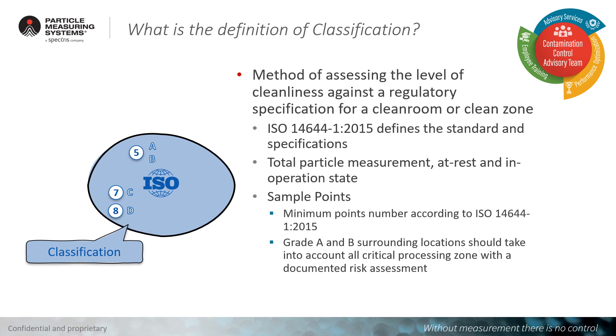The Annex 1 becomes aligned to the ISO regarding the classification points. We must follow the table that we can find inside the ISO, with just one peculiarity: we must take care to analyse all critical processing zones with a documented risk assessment where we want to classify grades A and B. This is not the same risk assessment as for monitoring, because the focus here is to ensure coverage of all critical zones where the process is statistically present.